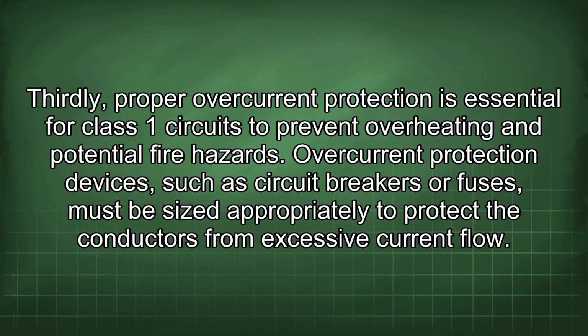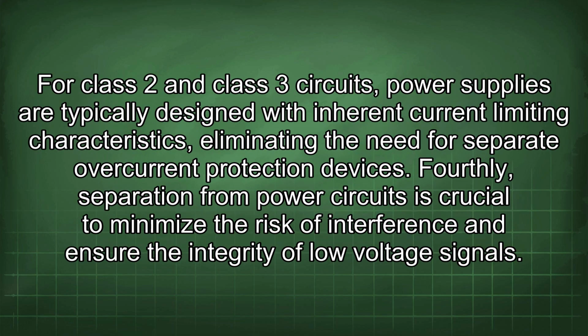Thirdly, proper overcurrent protection is essential for Class 1 circuits to prevent overheating and potential fire hazards. Overcurrent protection devices, such as circuit breakers or fuses, must be sized appropriately to protect the conductors from excessive current flow. For Class 2 and Class 3 circuits, power supplies are typically designed with inherent current limiting characteristics, eliminating the need for separate overcurrent protection devices.